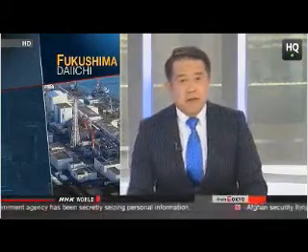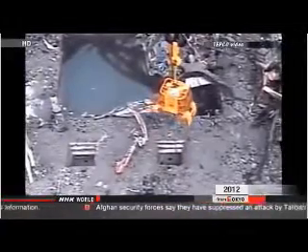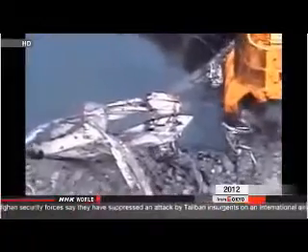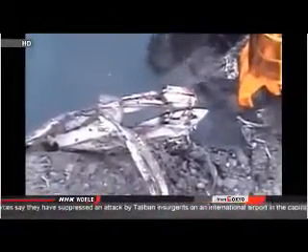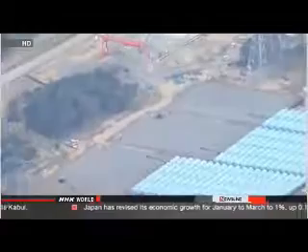Officials have been facing very challenging situations. In September, a crane operator accidentally knocked a steel beam into a spent fuel pool in the building of Reactor 3. The worker was removing debris at the time. A power blackout in March caused the suspension of cooling systems for spent fuel over nearly 30 hours. Officials believe a rat caused a short circuit in an electric switchboard.